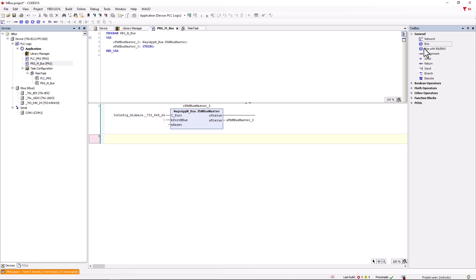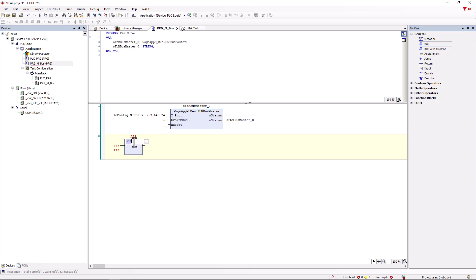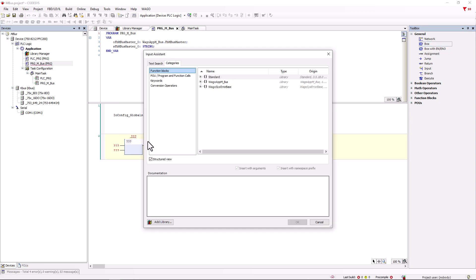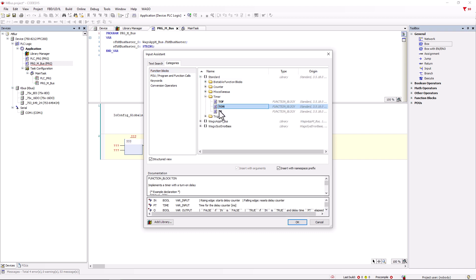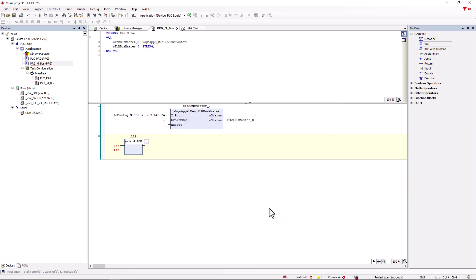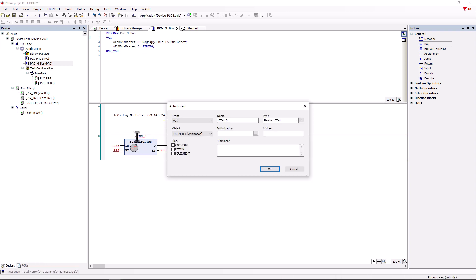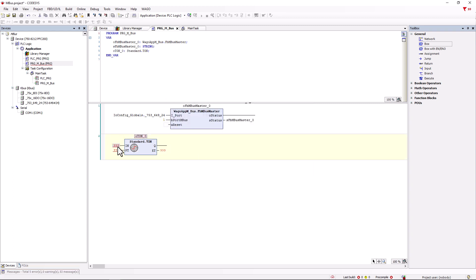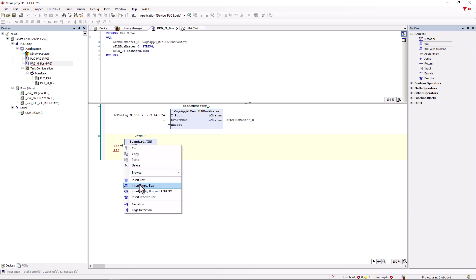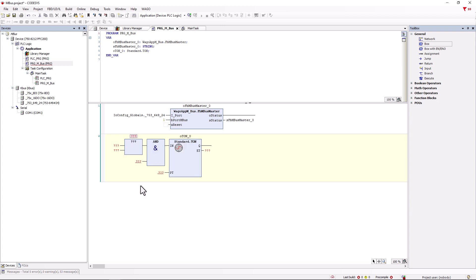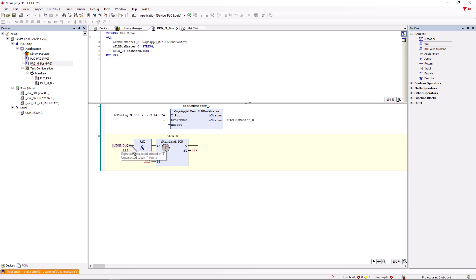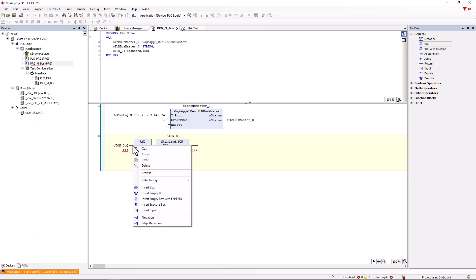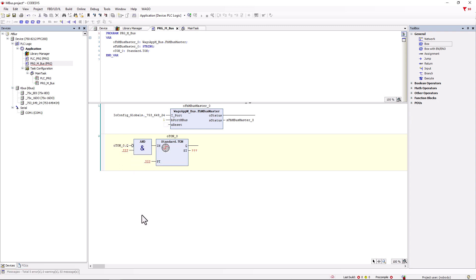Here too, we first add an empty box and define it in the input assistant as a timer module from the standard library with the function TON. With the function block TON, we generate a start variable that flashes regularly in order to trigger the MBUS query cyclically. We assign the name TON_0. At the IN input of the module, we need an AND gate which we can insert by right clicking on the input and insert empty box for example. We only need the AND gate. One input of the AND gate is the output of the TON module, which is TON_0.q and this must still be negated so that the time is re-triggered whenever the module falls back to false.